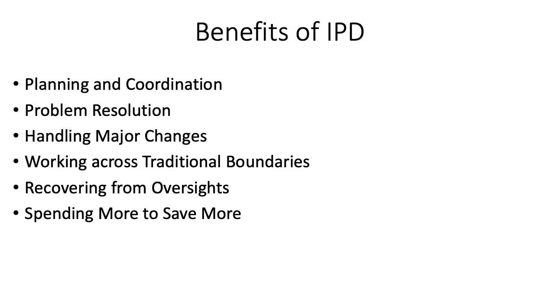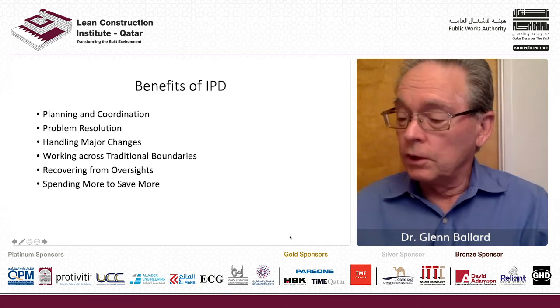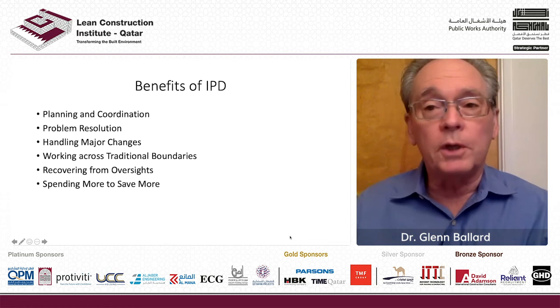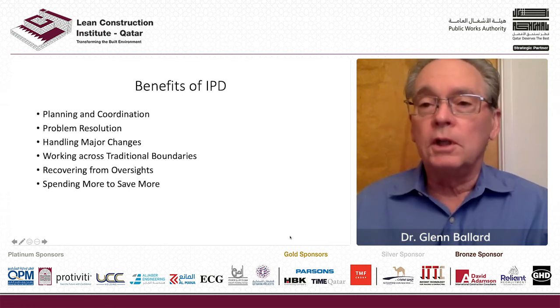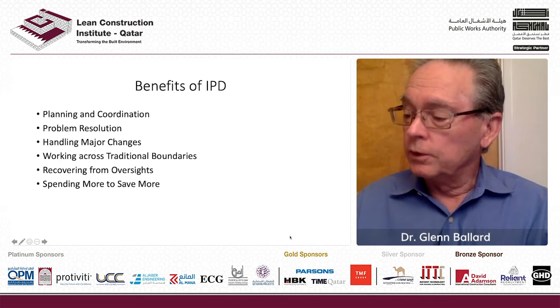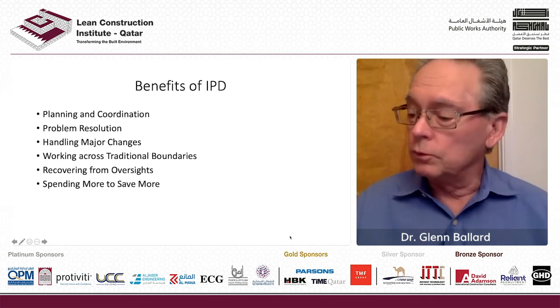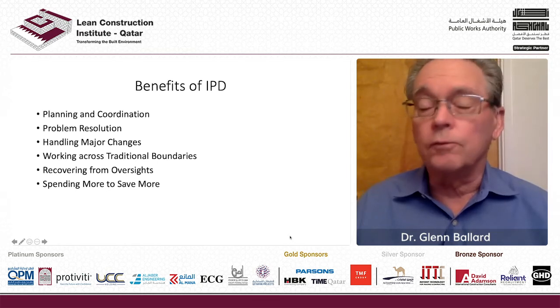Spending more to save more. Normally the design engineer prepares design drawings from which the contractor prepares shop drawings for fabrication. Major changes in layout can arise during this translation, and often do. On one project, the engineer sent his designer to the mechanical contractor's office, where the designer worked with an experienced mechanical piping expert to lay out the equipment room in detail using object-based modeling. This increased engineering cost at first but saved money downstream, since the mechanical contractor did not have to produce shop drawings because the engineering drawings were sufficient for fabrication.